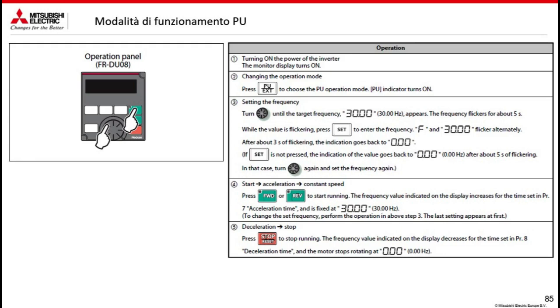So it says, now I am showing 0, but rest assured that I took 30 Hz as it told me with the F. Once I have defined a frequency, I give it the start command, either forward or reverse for the sense of rotation. When you press forward or reverse, you will see that the frequency will begin to increase until it reaches the set point you defined. Obviously, in the time defined by the acceleration ramp, which is parameter 7. To stop it, you press the stop button, the red one, and it will stop with the ramp defined in parameter 8, then return to 0.